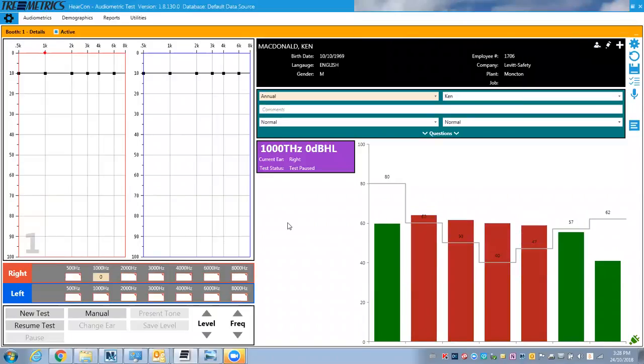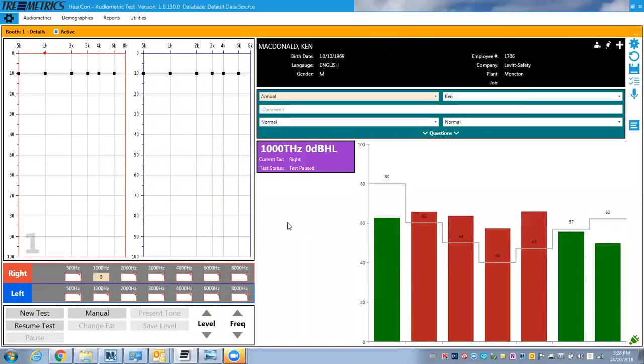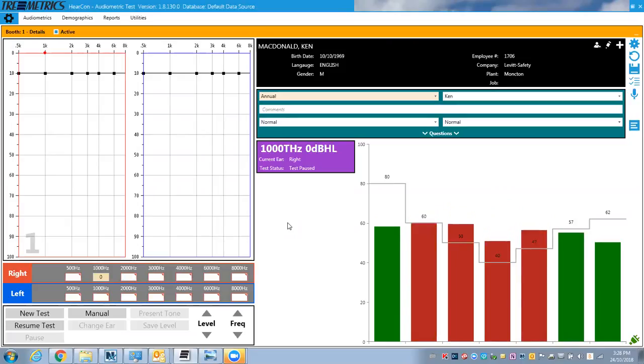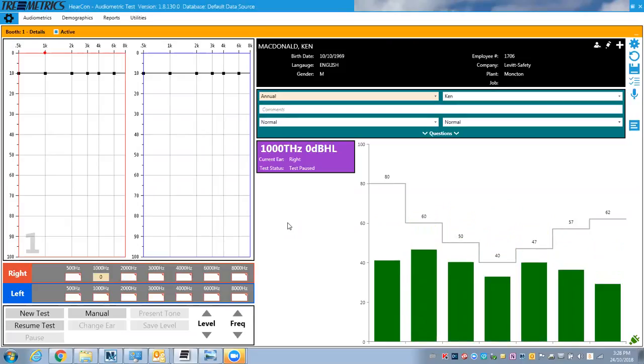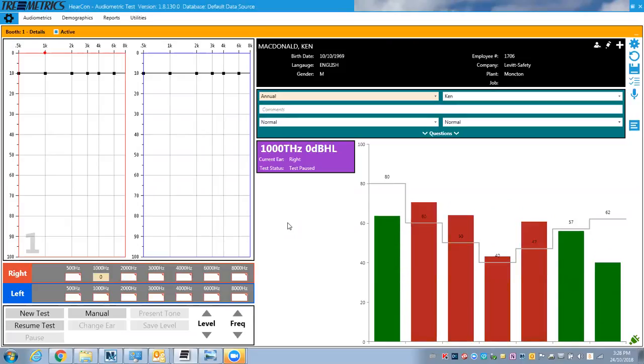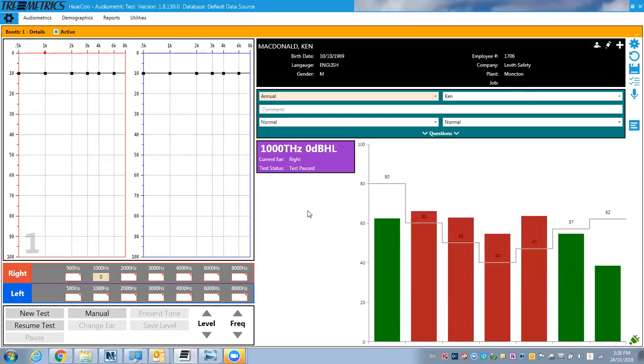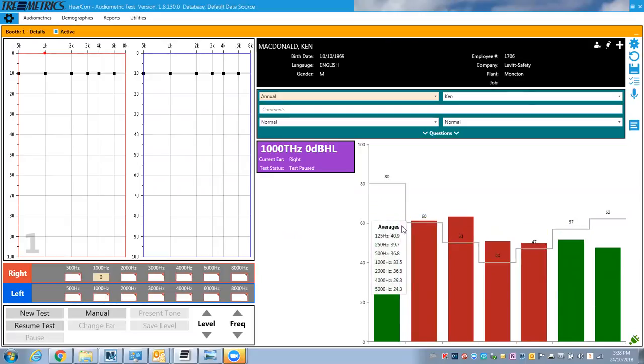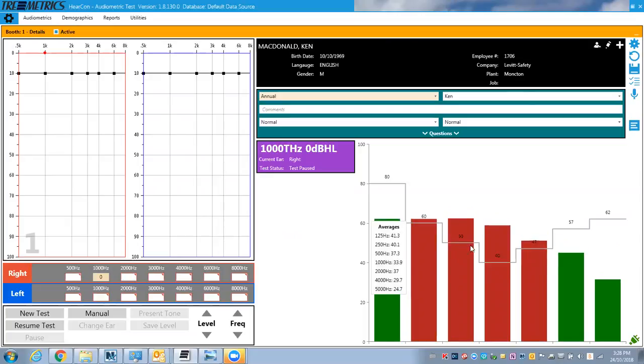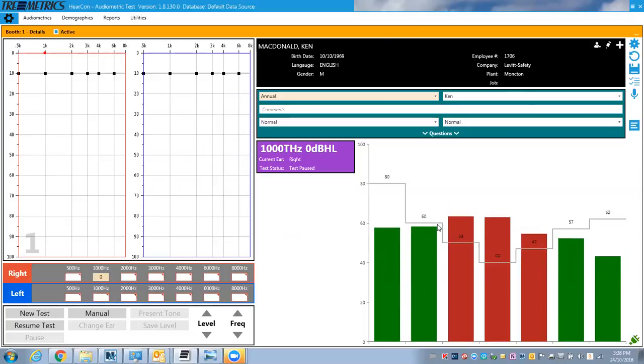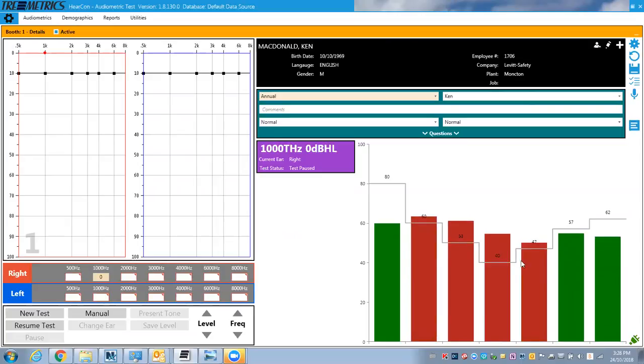This will be an overview of the Tremetrics HearCom software for the RA-660. This is the main page and one of the nice features of the RA-660 is that you can have this background room noise monitor that could pause the test if it goes above these settings that we've got set in here.